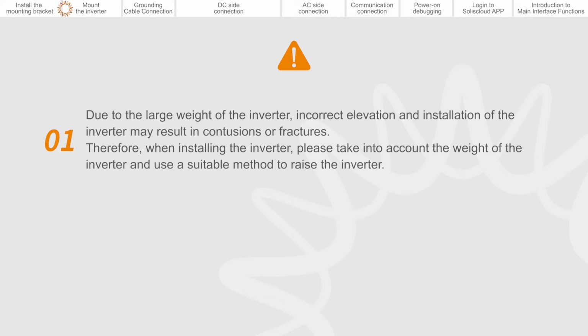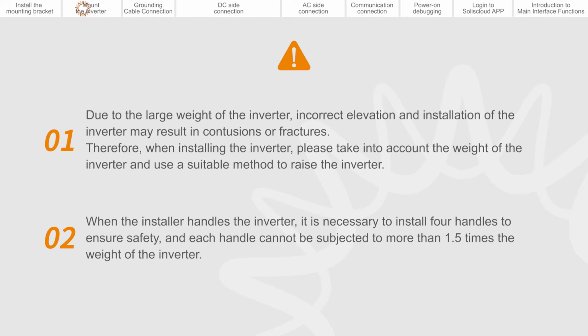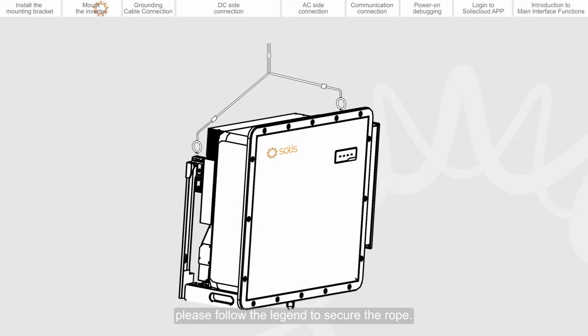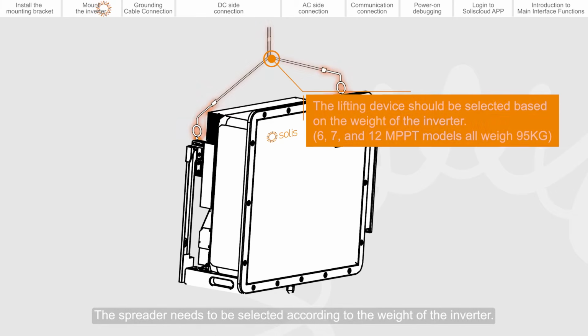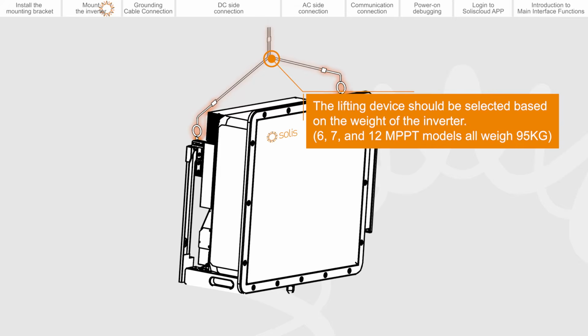Due to the large weight of the inverter, incorrect elevation and installation of the inverter may result in contusions or fractures. Therefore, when installing the inverter, please take into account the weight of the inverter, and use a suitable method to raise the inverter. When the installer handles the inverter, it is necessary to install 4 handles to ensure safety, and each handle cannot be subjected to more than 1.5 times the weight of the inverter. If hoisting is required, please follow the legend to secure the rope. The spreader needs to be selected according to the weight of the inverter.